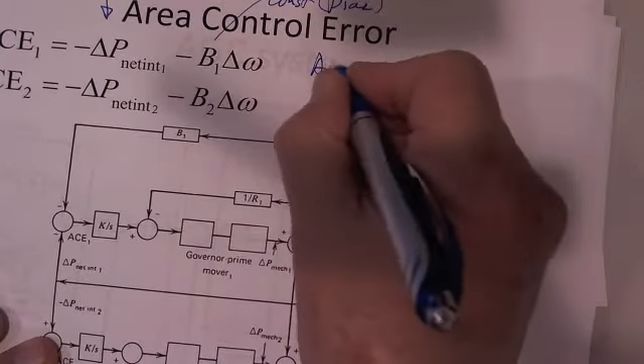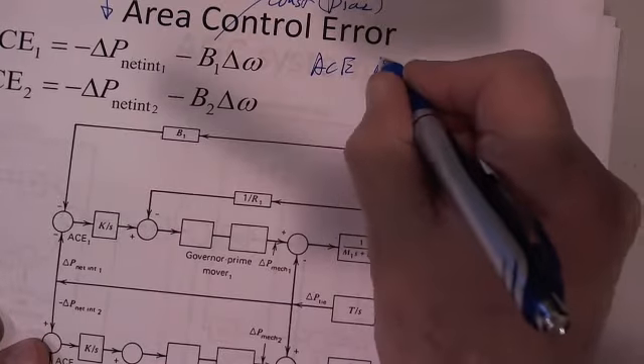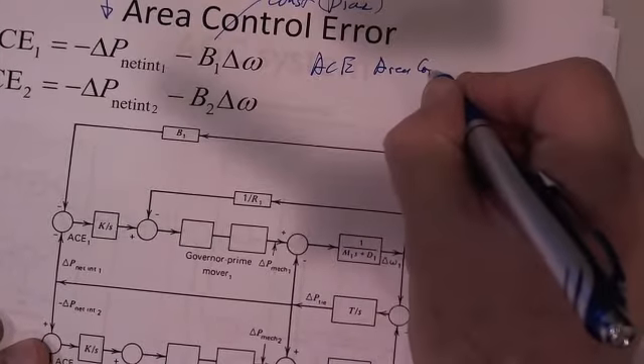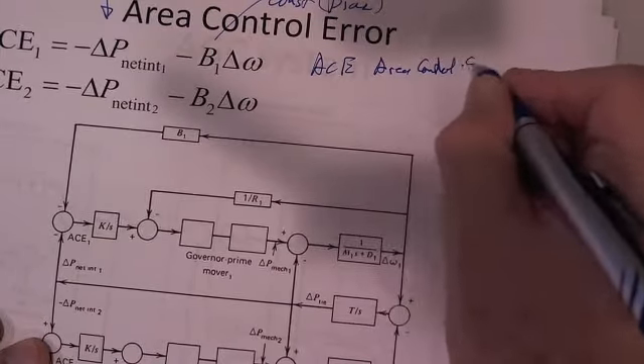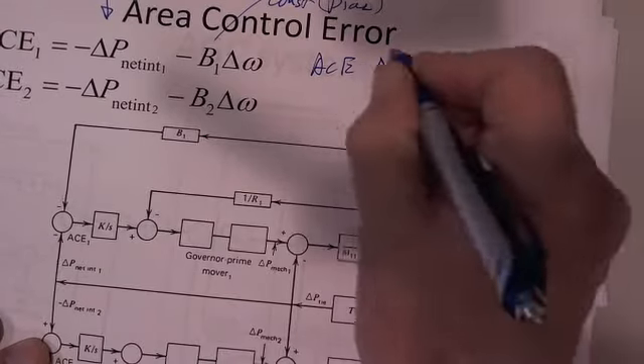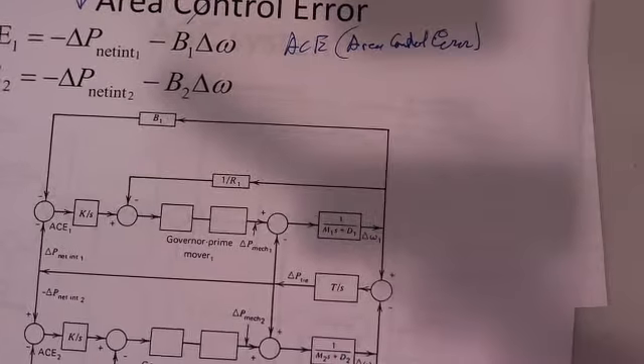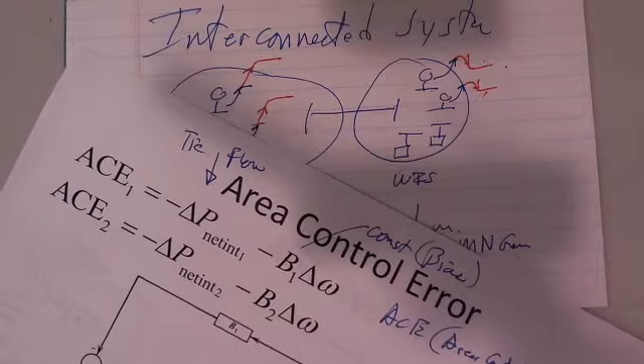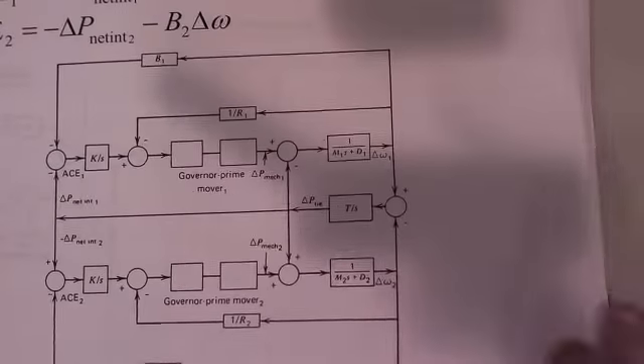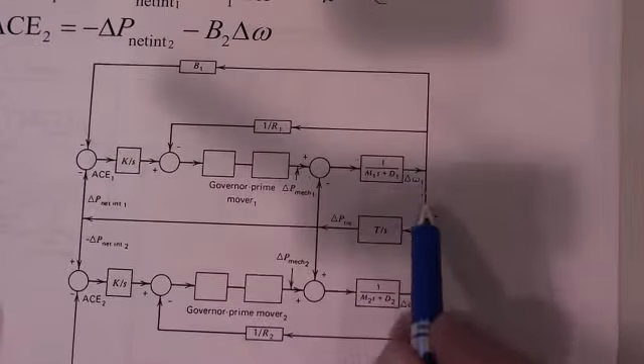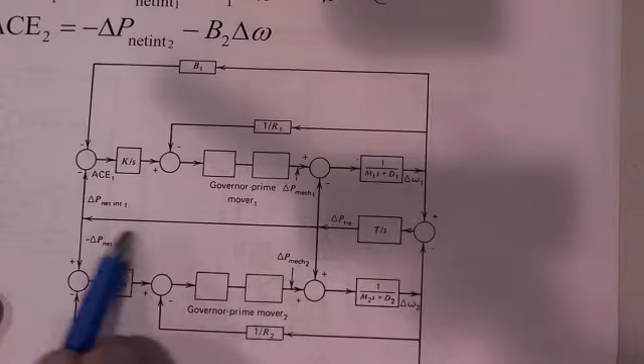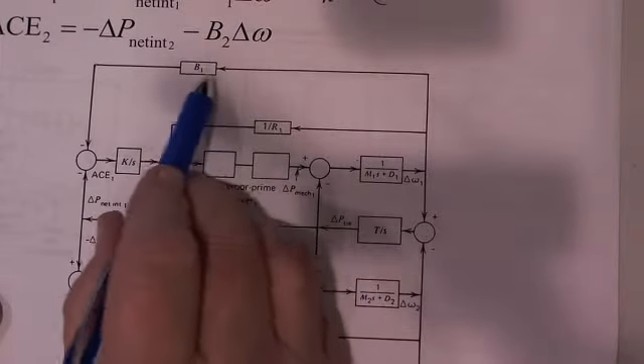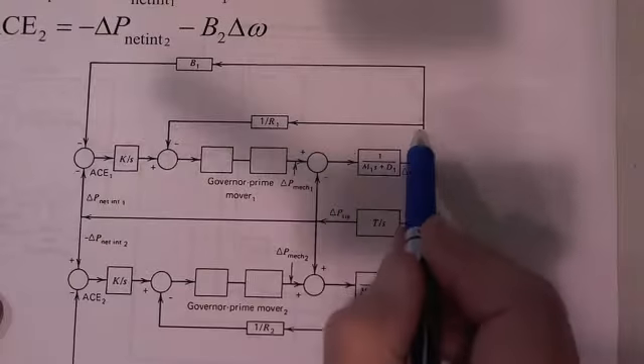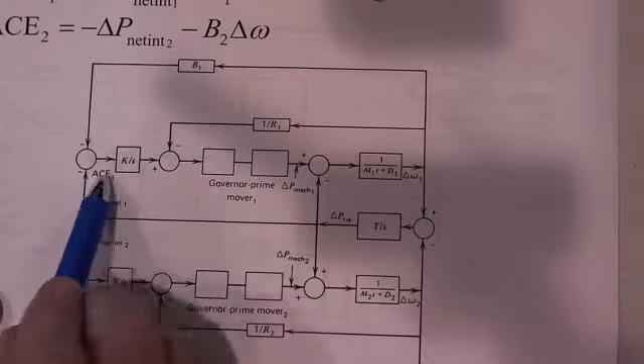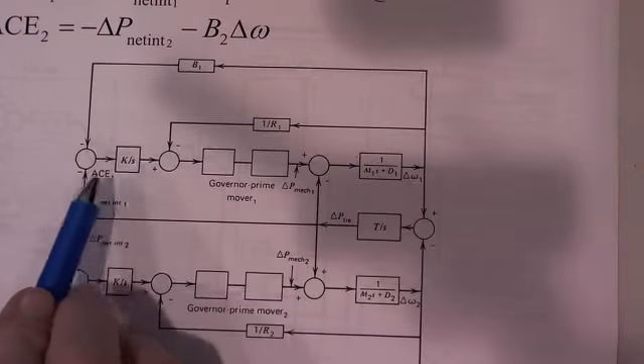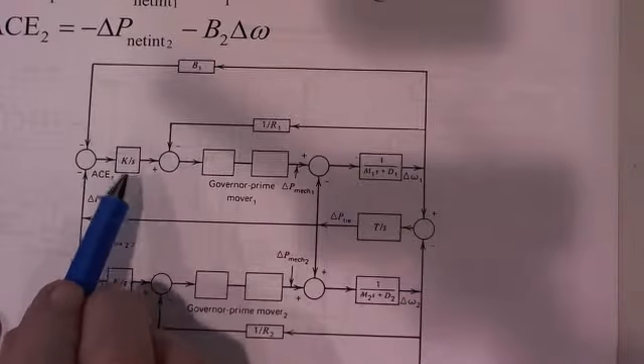And ACE, area control error, is still used. It is still the best way to do this. And you can see on this diagram how we took the delta tie flow and the bias times delta omega and combined them. We got ACE, and that was the system that we used to drive this.